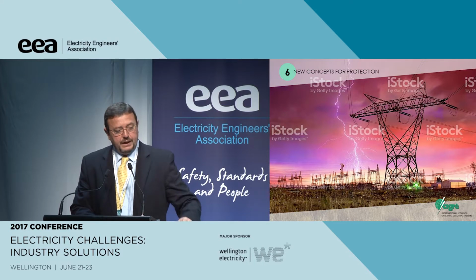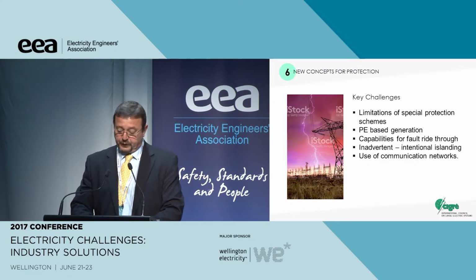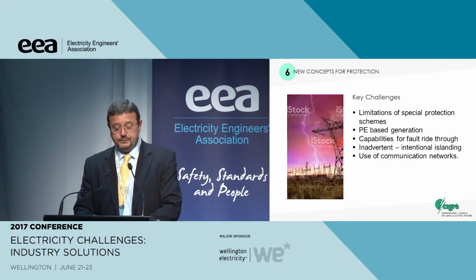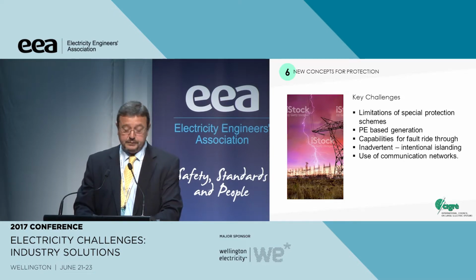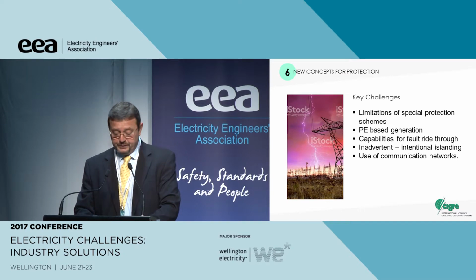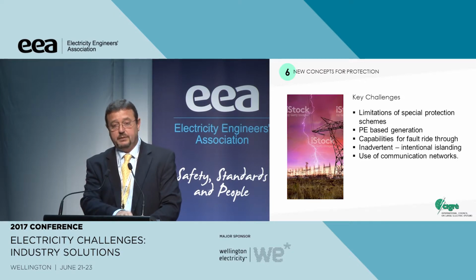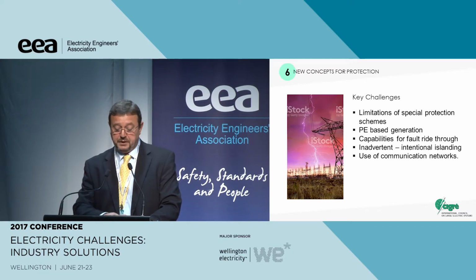New wide area protection systems for transmission to overcome limitations of special protection schemes in terms of reliability, flexibility, and maintenance costs. Impact of power electronic-based generation on the protection system due to decreasing short-circuit power and flow reversal.